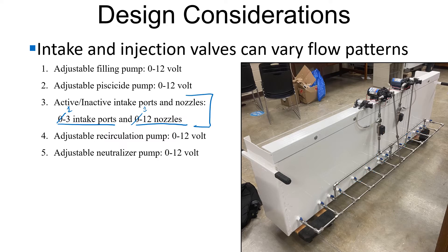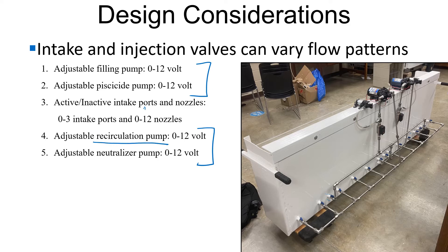The goal is to minimize the number of injection nozzles and intake ports needed in the full-scale ballast tank, since each costs money to drill, install, and pipe. On the right-hand side we have an adjustable filling pump and adjustable piscicide pump, both zero to 12 volts. The recirculation pump may not need to be used at all depending on vacuum in the intake line. The recirculation pump is the large one, and the smaller neutralizer pump is connected on the vacuum end.